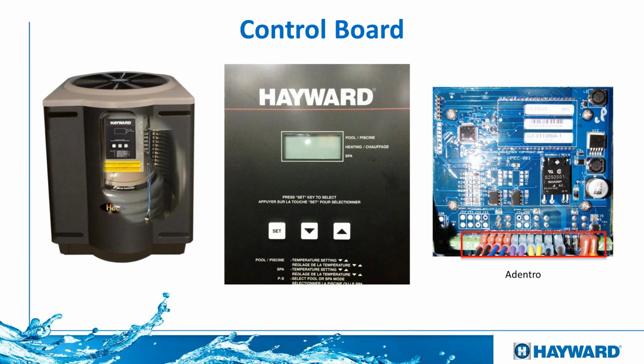Two yellow wires here are for the compressor. These two are the ones that send the voltage to the contactor so it can close and send voltage to the compressor so it can turn on. That's 24 volts that go out. So if we want to see if they're working or not, simply turn on the heater and then make sure the contactor is closed, and you will see it in a second.